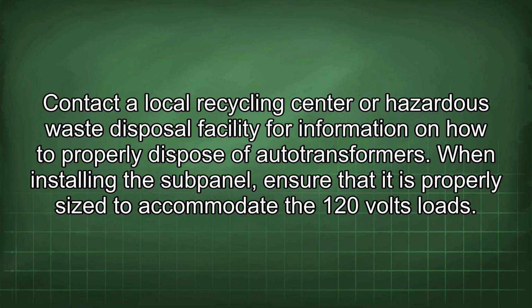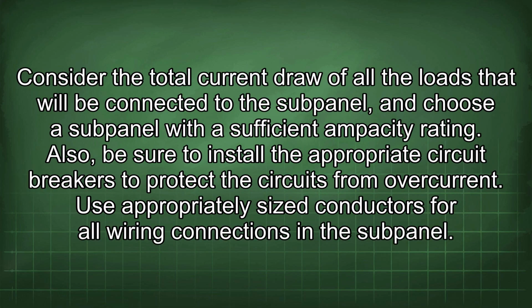When installing the subpanel, ensure that it is properly sized to accommodate the 120 volt loads. Consider the total current draw of all the loads that will be connected to the subpanel and choose a subpanel with a sufficient ampacity rating. Also, be sure to install the appropriate circuit breakers to protect the circuits from overcurrent.